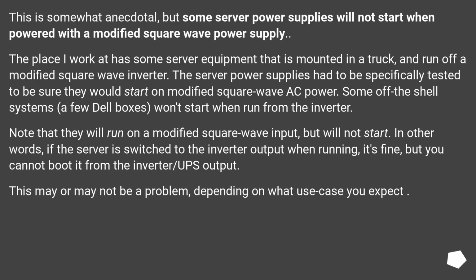This is somewhat anecdotal, but some server power supplies will not start when powered with a modified square wave power supply. The place I work at has some server equipment that is mounted in a truck and run off a modified square wave inverter. The server power supplies had to be specifically tested to be sure they would start on modified square wave AC power. Some off-the-shelf systems, a few Dell boxes, won't start when run from the inverter. Note that they will run on a modified square wave input, but will not start. In other words, if the server is switched to the inverter output when running, it's fine, but you cannot boot it from the inverter/UPS output. This may or may not be a problem, depending on what use case you expect.